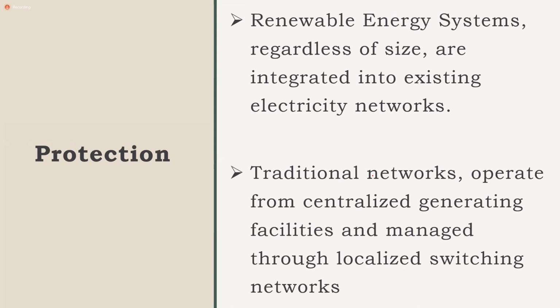In terms of how the network is set up generally, you're going to have different protection at different points. Even at the distribution level you still have your fuses, and in some instances at distribution you have self-protected transformers, SPTs, which are transformers that carry a breaker on them. So you have your protection at the transmission level and at the distribution level.